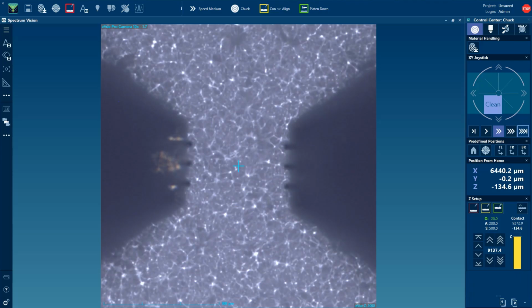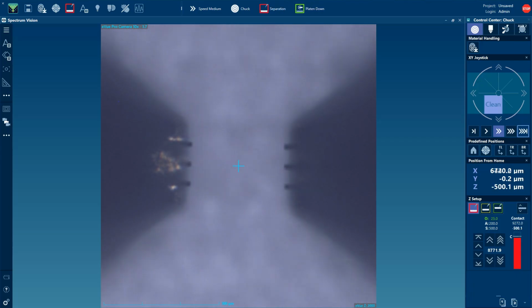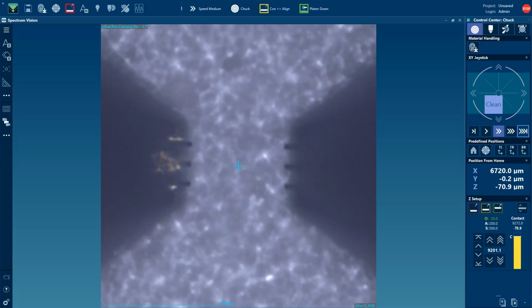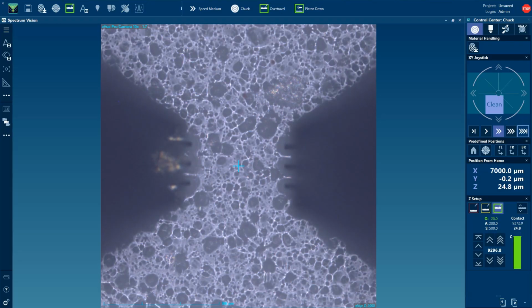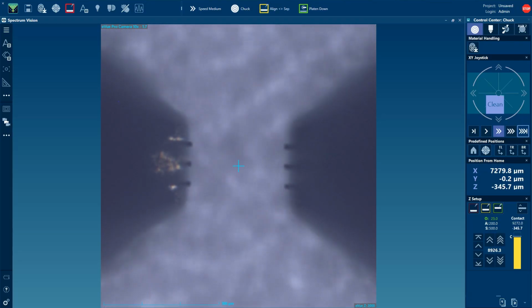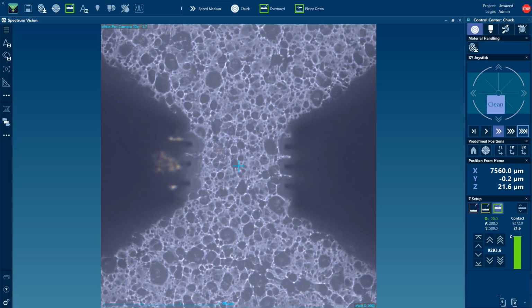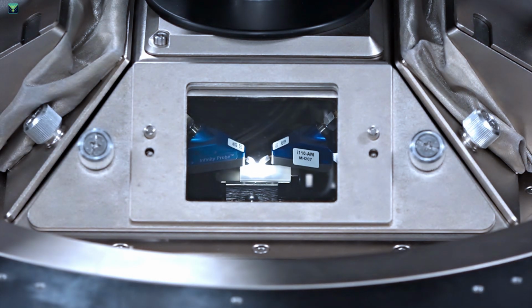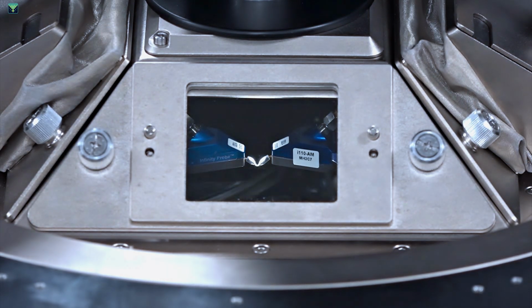Cleaning step patterns in Velox define how cleaning substrates of type pad cleaner are moved underneath the probe tips between each cleaning touchdown. Choosing the best cleaning step pattern for your probes ensures that each touchdown occurs on a fresh cleaning area, preventing contamination and ensuring best measurement performance.